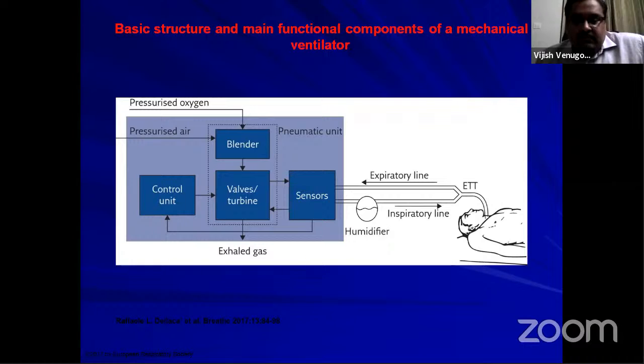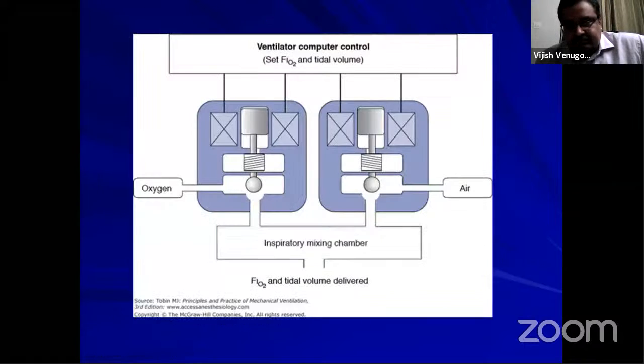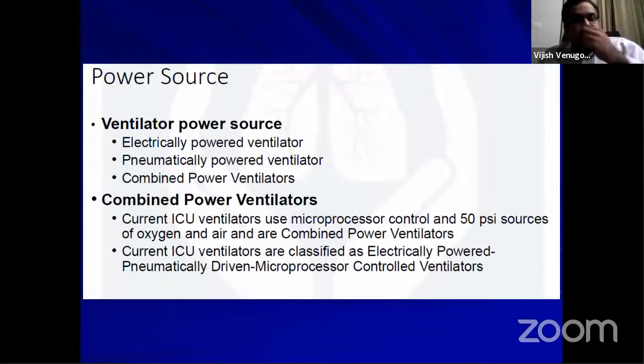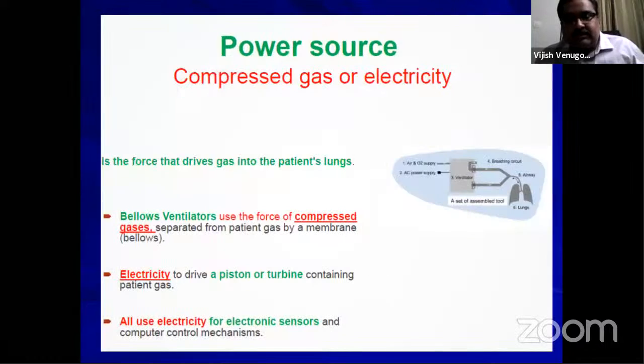And then it will give you a feedback mechanism, and the feedback mechanism is going back to the control unit. So this is how a basic ventilator works. This is the small picture of the blender. And the power source could be an electrically powered or pneumatically powered ventilator, but the current ICU ventilators use microprocessor control. So they are classified as both electrically powered, pneumatically driven, and microprocessor controlled ventilators.